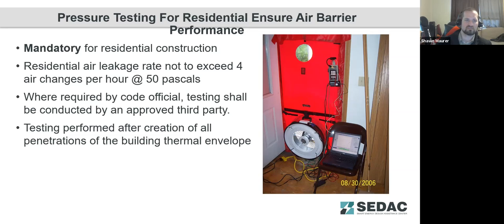But this test just pressurizes or depressurizes the building to a standardized test pressure. For residential, it's 50 pascals. And per the energy code, it's not to exceed 4 air changes per hour in the state of Illinois. If you're outside the state of Illinois for a project, that is 3 air changes per hour at 50 pascals, and Illinois should be moving towards that rating for the next version of the energy codes coming in the summer of 2022. But this testing is a great way to verify that you've checked all your things in your plan drawings, made sure those details were correct, and you went out on site and checked them. This is an excellent way, the ideal way, to verify that you haven't missed something that was hidden somewhere.